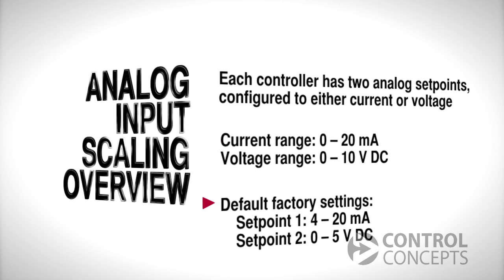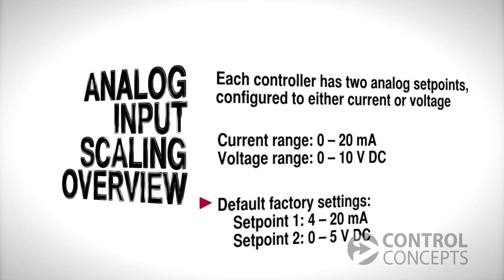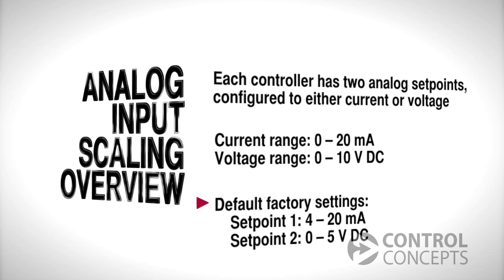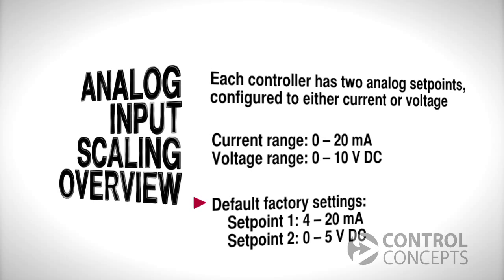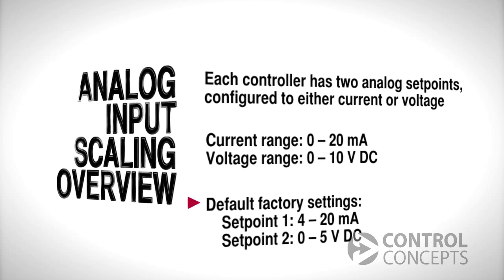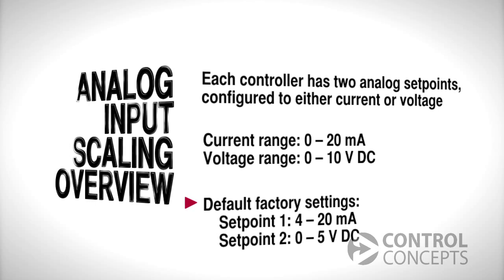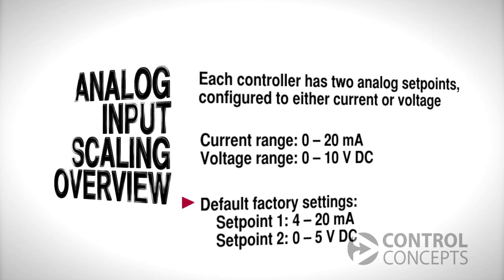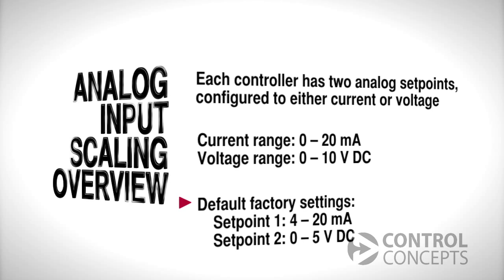Our default factory settings have set point 1 configured for 4 to 20 milliamps current input and set point 2 configured for 0 to 5 volts DC voltage input.